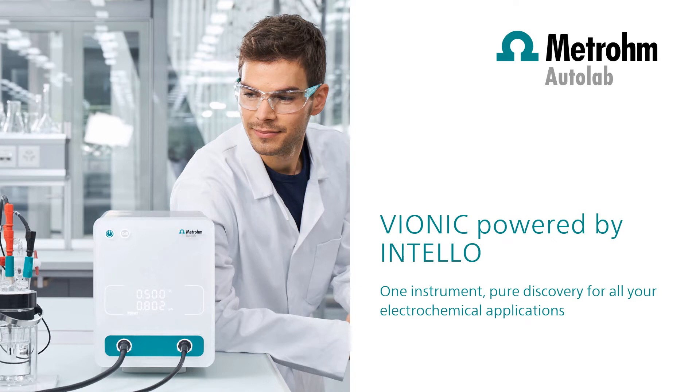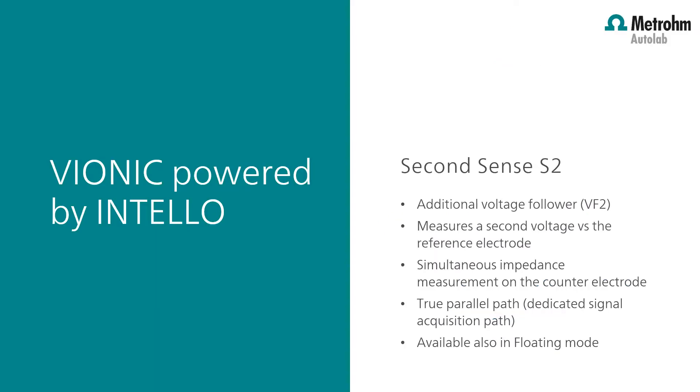Welcome to INTELLO videos. In this video I would like to show you the functionality of the second sense electrode. The second sense electrode, or S2, is an additional voltage follower which can measure a second voltage versus the reference electrode, for example the potential on the counter electrode within the same electrochemical cell. It's also possible to measure the impedance on the counter electrode with the S2 electrode.